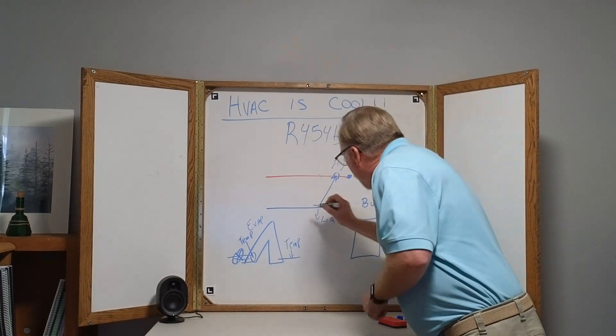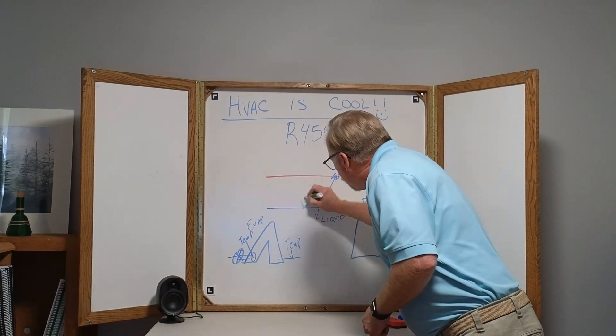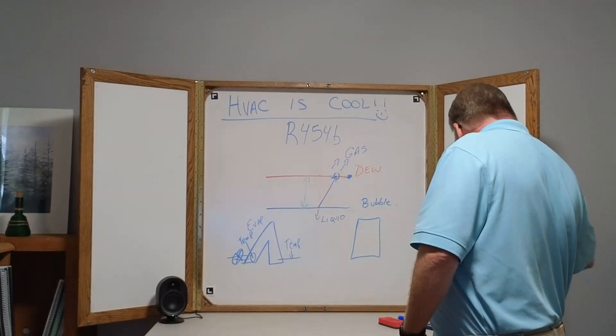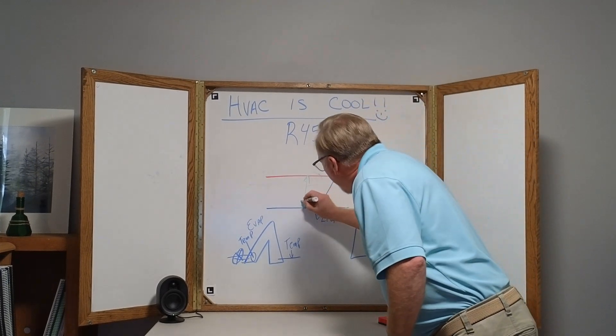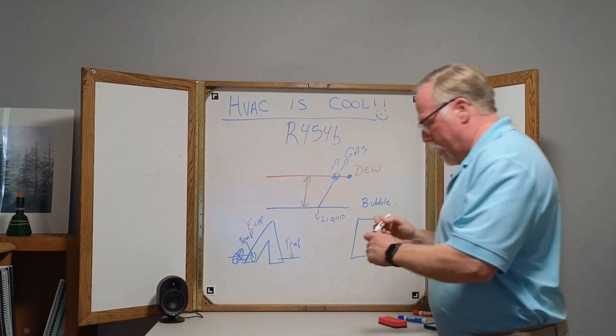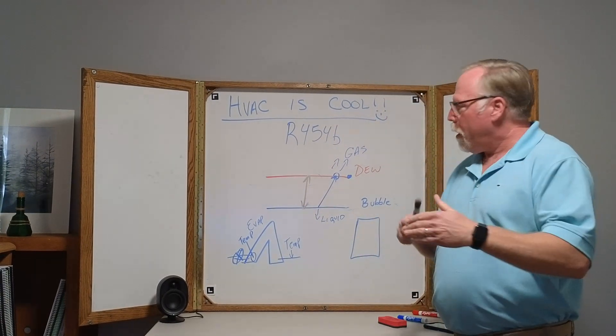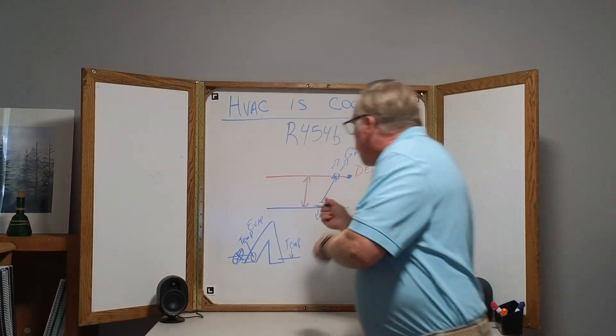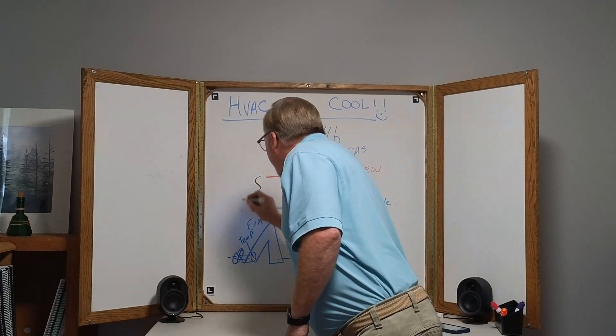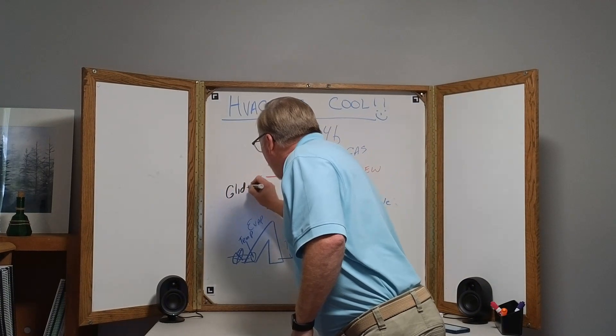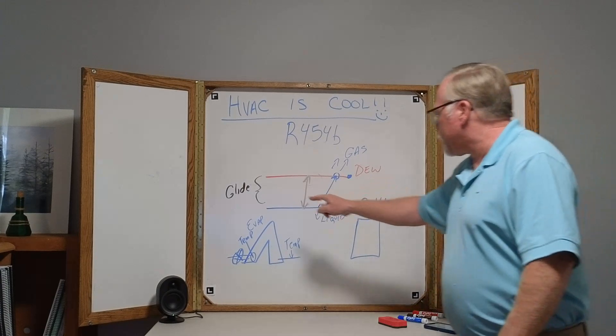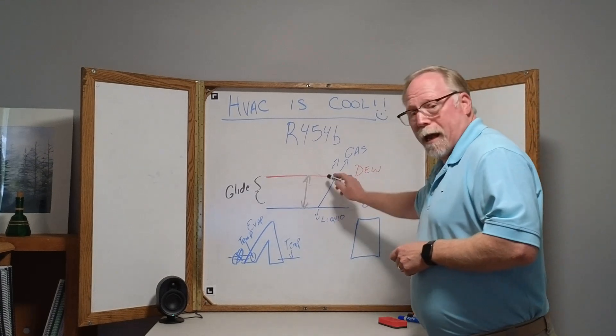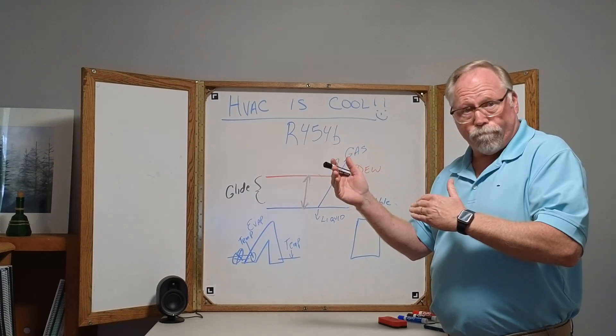In between bubble and dew point, anything in between those two lines, the bubble and the dew, the refrigerant is still changing phase. There's a glide now. That glide is happening between the bubble point and the dew point. This is the glide temperature. The pressures stay the same, by the way. It's just the temperature that's changing somewhat.